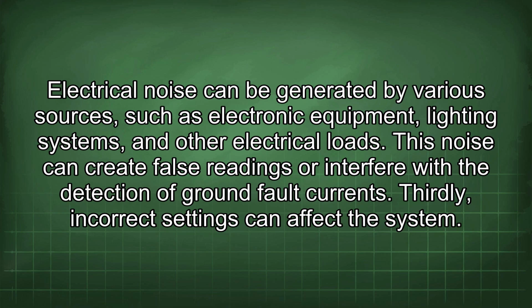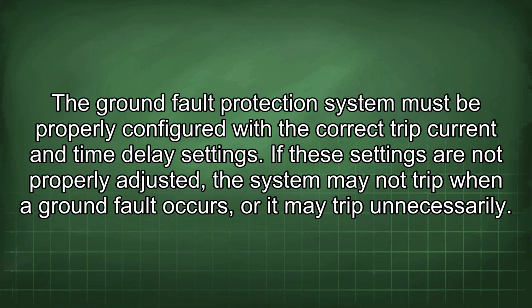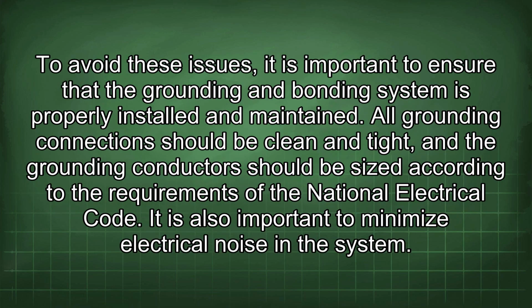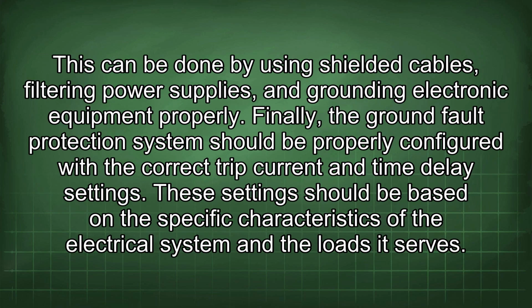Thirdly, incorrect settings can affect the system. The ground fault protection system must be properly configured with the correct trip current and time delay settings. If these settings are not properly adjusted, the system may not trip when a ground fault occurs, or it may trip unnecessarily. To avoid these issues, it is important to ensure that the grounding and bonding system is properly installed and maintained. All grounding connections should be clean and tight, and the grounding conductors should be sized according to the requirements of the National Electrical Code. It is also important to minimize electrical noise in the system. This can be done by using shielded cables, filtering power supplies, and grounding electronic equipment properly.